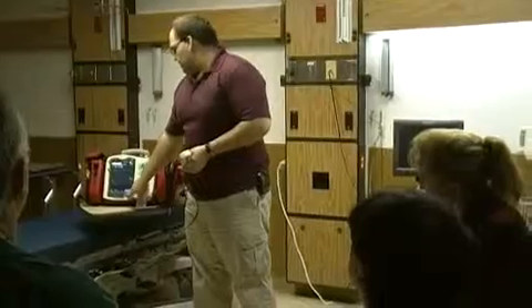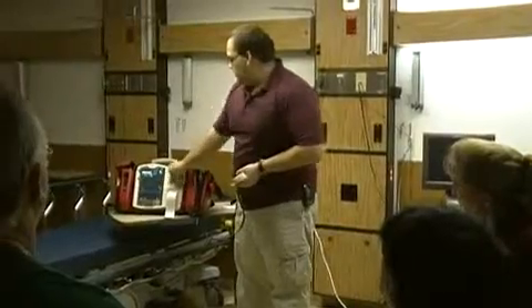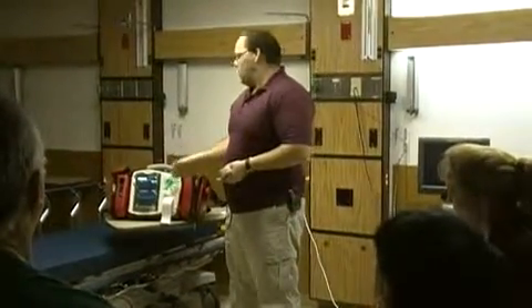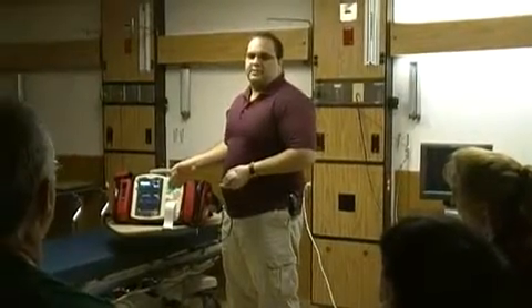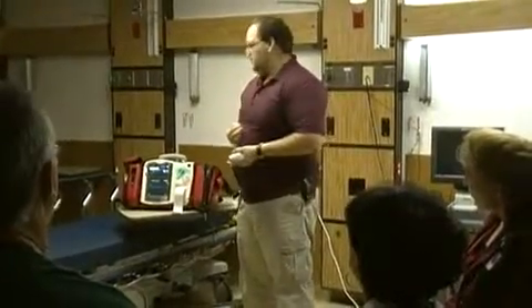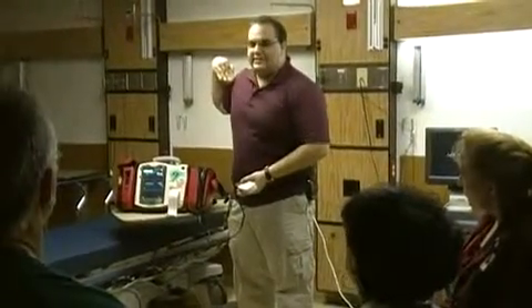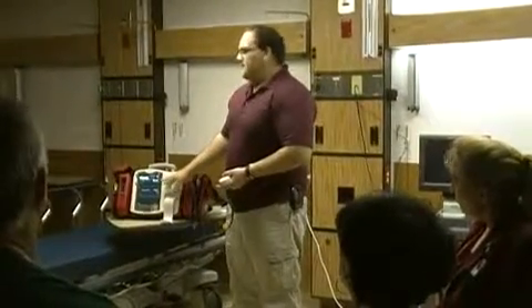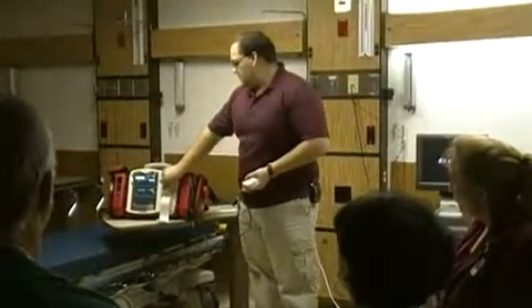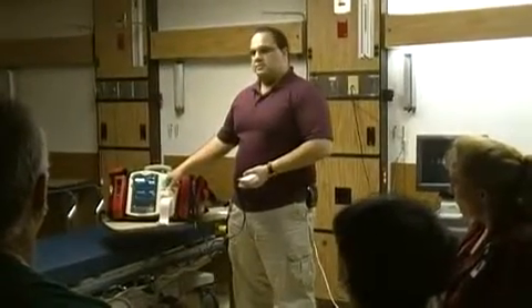Only two rhythms that we're going to shock are ventricular fibrillation and ventricular tachycardia. Currently on this machine, the adult dose is set to 150 joules, and it is smart biphasic. In other words, what that means is it measures the impedance and adjusts for it, so a bigger guy like me is going to need more electricity, and it'll adjust that. Biphasic means it's going to go through one way, immediately right back the other way. Instead of the old monophasic where it just goes 360 joules one way, this is going to go 150 one way, right back down the other. If 150 is not effective and there's refractory VFib, VTach, you can actually set it up to 200 joules. Shock from there.